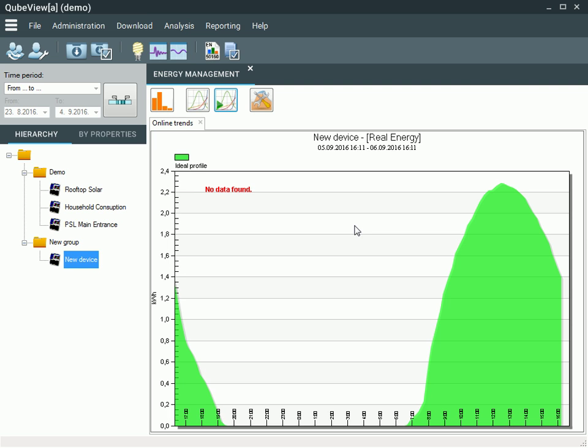But in the background, the software started to communicate with the PCube device, and it started to read out its meter's HTML page, parse out that information, and aggregate it into 1-minute measurements stored in the SQL database. So if I keep this window open for some time, I would start seeing a red line appearing from the right, showing the current live measurements.